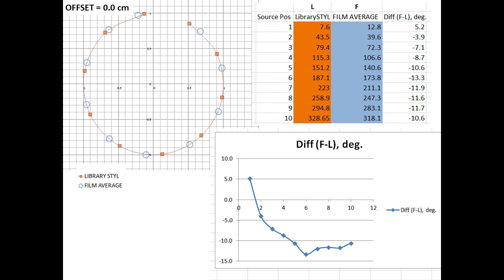So for offset 0 centimeters, the differences in angular source position between library and film are compared on this graph. For most source positions the differences are more than the tolerance level, 2 mm or 7 degrees, as mentioned in various technical documents and guidelines. That is why these source positions need to be somehow corrected. In theory that correction can be done by using the so-called zigzag method. Zigzag, or shortening the source travel path between the first and second source positions, keeps position number 1 on the same plane, but positions 2 to 10 are rotated clockwise by the needed angular value.